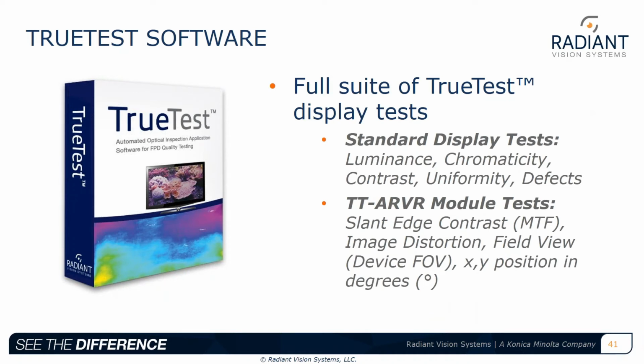TrueTest software is something that would probably be important to come along with this device. TrueTest is a testing sequencer software that can control a testing suite. We have a number of tests that are available that are good for standard displays. We've also developed a number of tests that are pretty good for this specific application. So things like slant edge MTF, image distortion, measuring the device's field of view, and then also having the system read out in degrees.